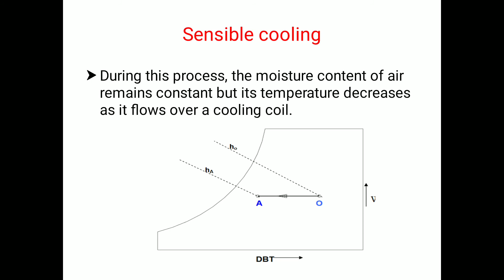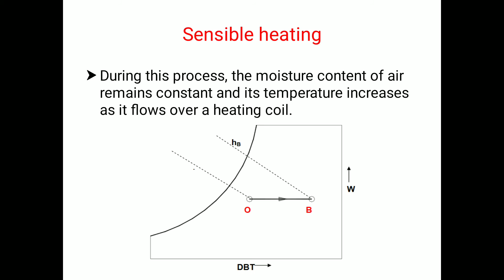So next, we will see what the sensible heating process is. Like the sensible cooling process, the sensible heating process is also without any change in specific humidity; we are going to heat the air. So this process is known as sensible heating. If you observe the psychrometric chart, the process O to B is known as sensible heating. During this process, the moisture content of air remains constant, as we already said, and its temperature gets increased due to the heating. We can use a heating coil for this heating purpose, and we can use a cooling coil for the sensible cooling process.